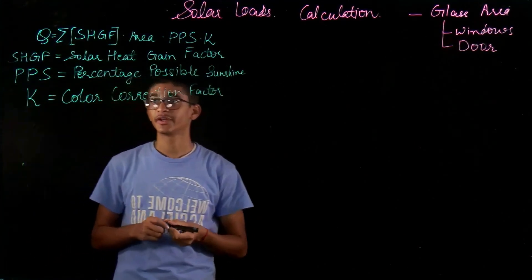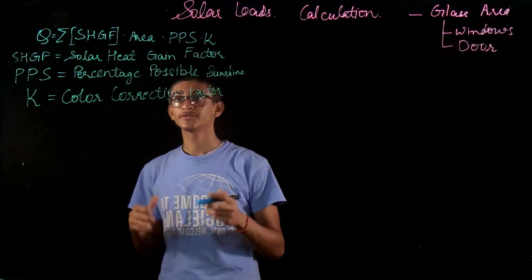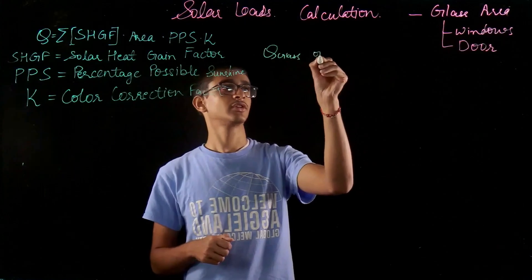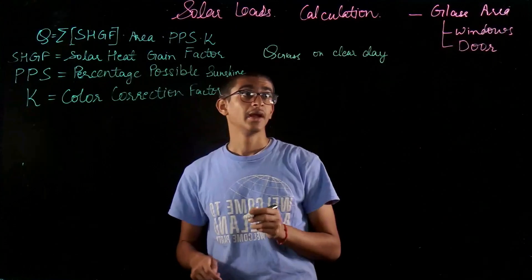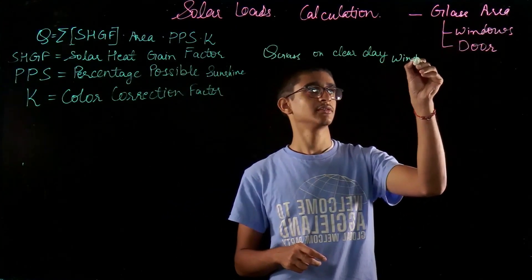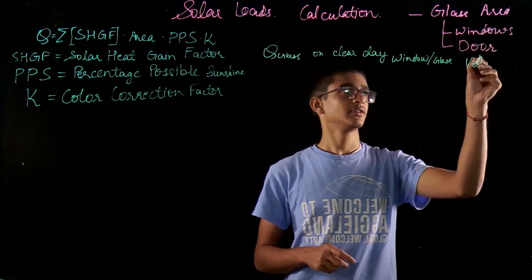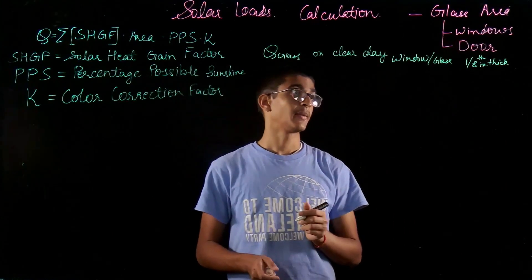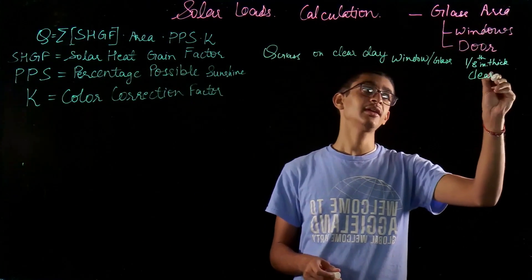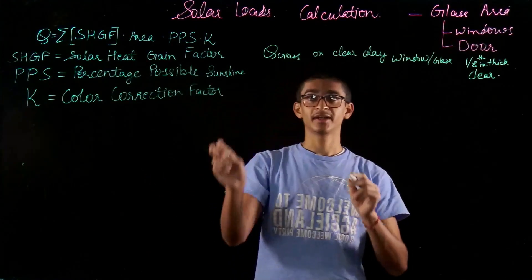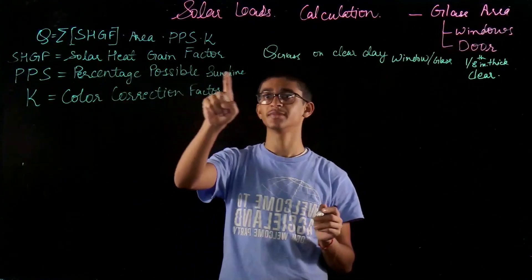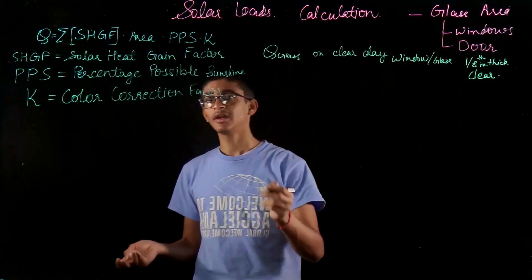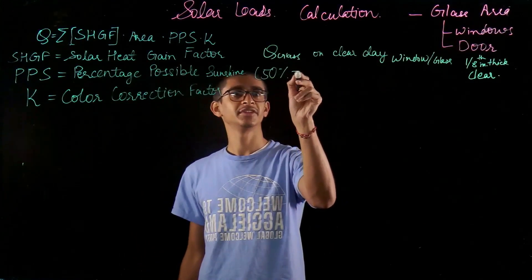PPS is also an important factor, which is percentage possible sunshine. And K is the color correction factor. What SHGF represents is the amount of solar heat gain which is happening through the windows or glass on a clear day, through a window or glass which is one-eighth inch thick, and it is a clear glass. If it is not a clear day, there are some clouds, we'll take into account this factor which is PPS, which says percentage possible sunshine.